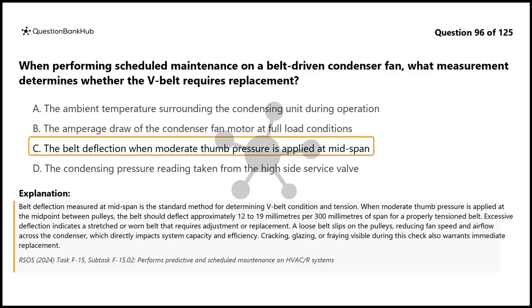A loose belt slips on the pulleys, reducing fan speed and airflow across the condenser, which directly impacts system capacity and efficiency. Cracking, glazing, or fraying visible during this check also warrants immediate replacement.